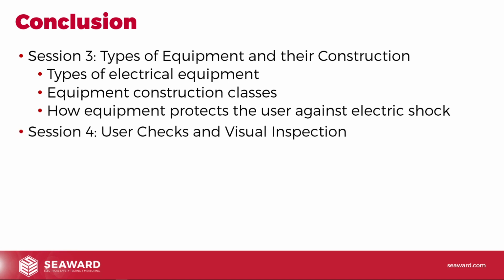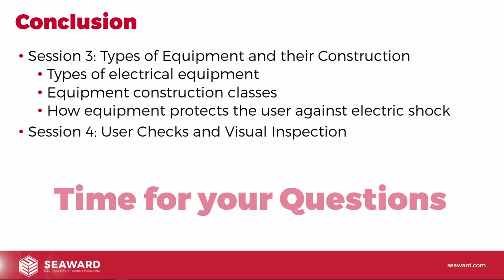So moving on to next week, session 4, we're actually going to get on to doing a bit of visual inspection. We're going to look at the user checks, so the checks that a user carries out when they're checking a piece of equipment, maybe doing a daily or weekly user check, and then we're going to look at the formal visual inspection, so how a competent person who's actually carrying out PAT testing would start off and carry out a visual inspection, what we're going to be looking for and what items we need to check there when we're carrying out a visual inspection on equipment.